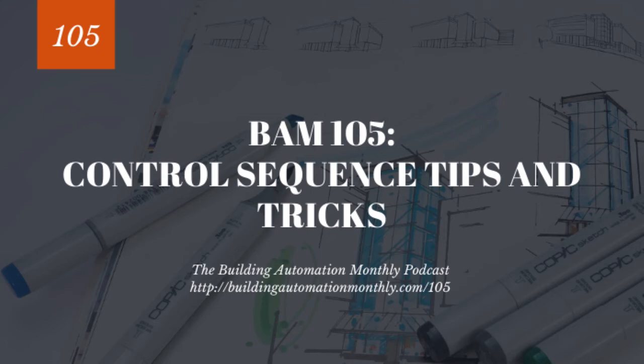So naturally, what do you think most people would do? Most people are going to say, well, I need to turn on the heat at the unit because the unit's not heating up the discharge air, and the space just isn't going to heat up. I need to turn on the heat because that's why they got heat in the unit. It's a reheat unit. It needs the heat. Okay, so let's do that. But what would happen? Well, all those other spaces that are satisfied, what do you think's going to happen to them? They're all going to get hot, right? Because right now they're at set point without the heat on. I turn the heat on, they all get hot.